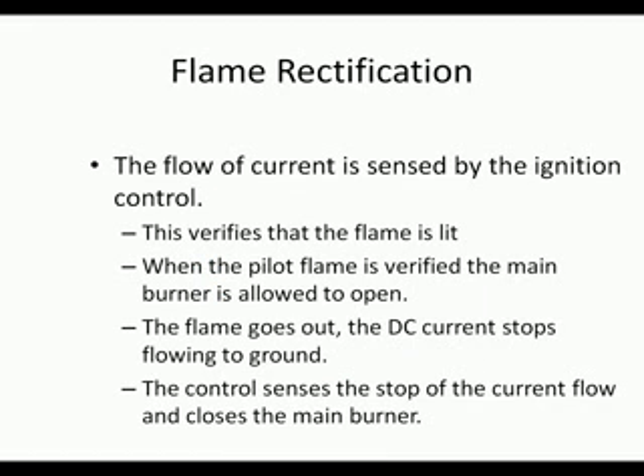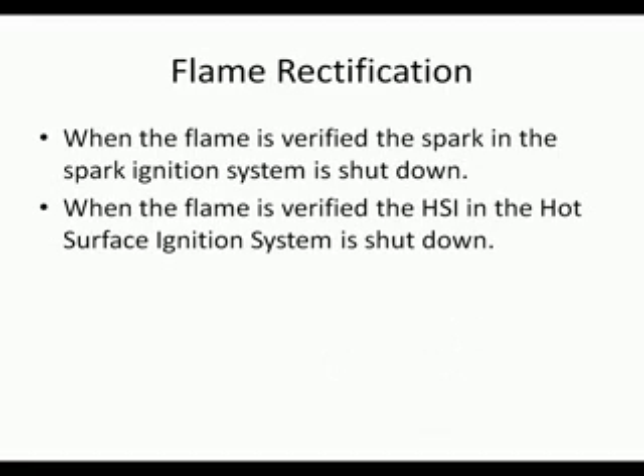This is an example of testing flame rectification. You have your flame rod that is connected to the flame sensor terminal on the ignition module. You take your meter lead and put it from the burner ground to the burner ground terminal on the ignition module. Change your meter to microamps and read what it says. You should have about a 2 microamps current flow. The flow of current is sensed by the ignition control. This verifies that the flame is lit.